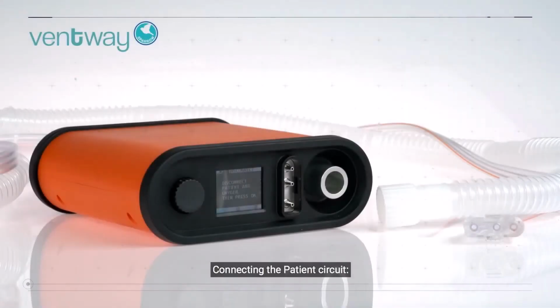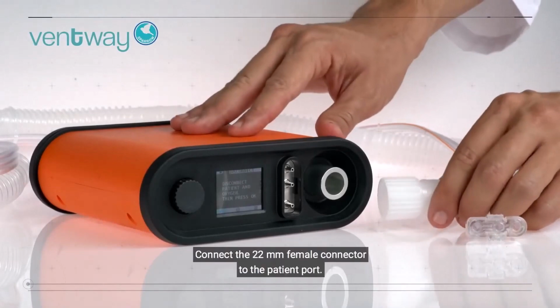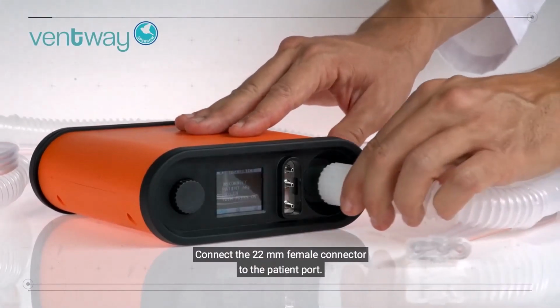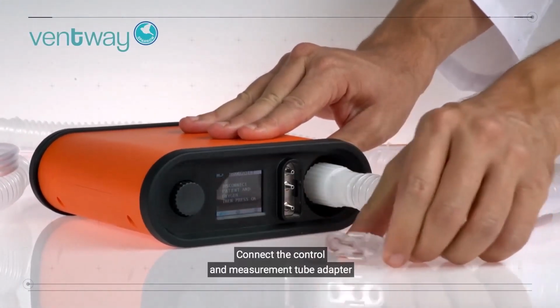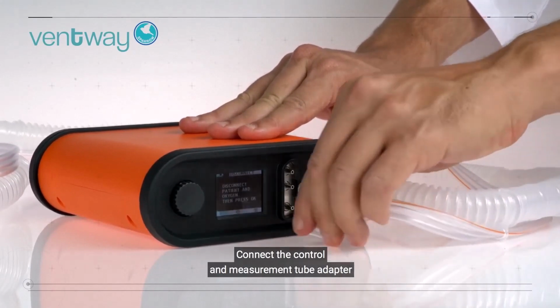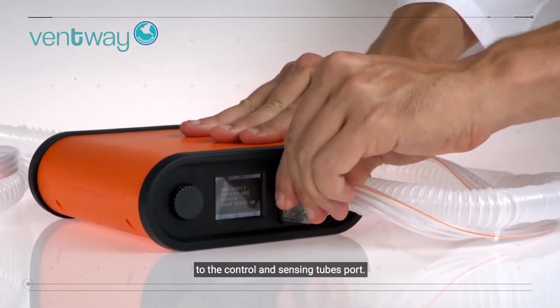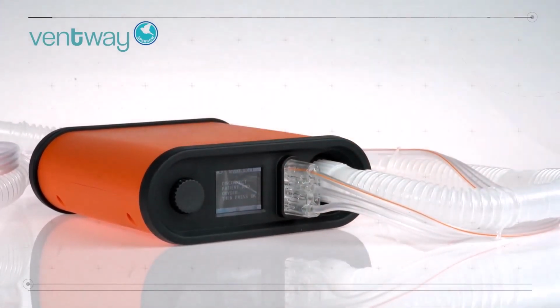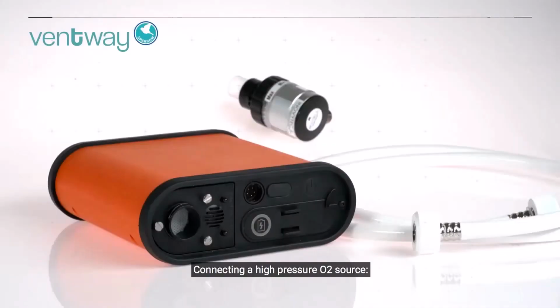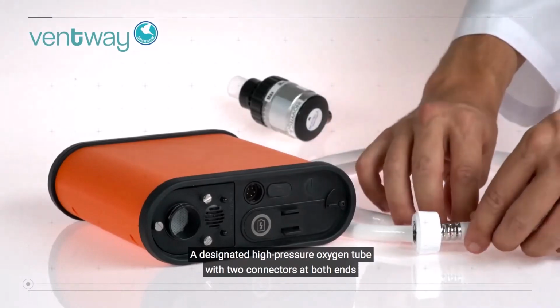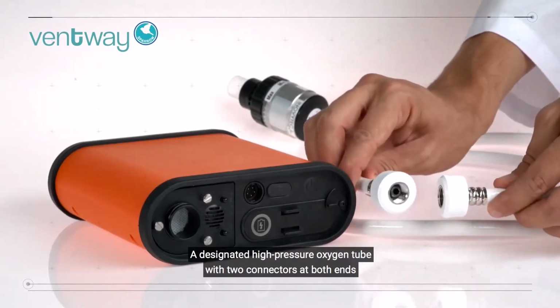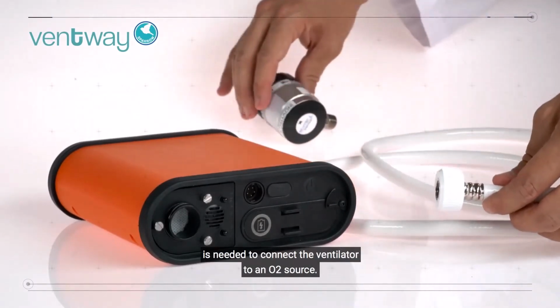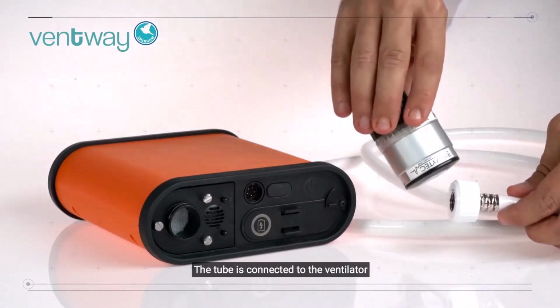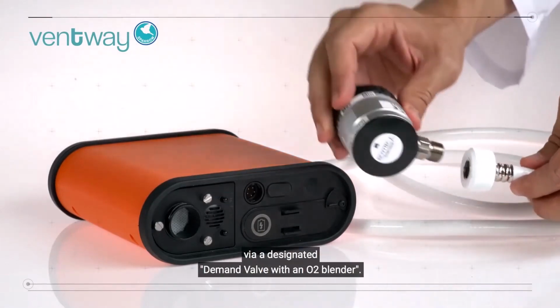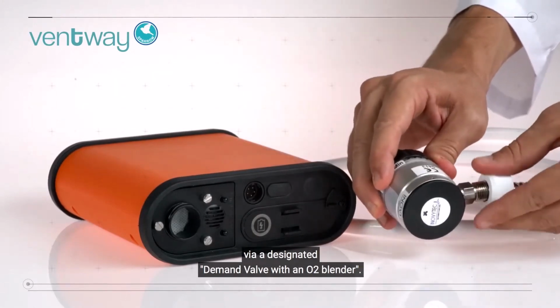Connecting the patient circuit. Connect the 22 mm female connector to the patient port. Connect the control and measurement tube adapter to the control and sensing tubes port. Connecting a high-pressure O2 source. A designated high-pressure oxygen tube with two connectors at both ends is needed to connect the ventilator to an O2 source. The tube is connected to the ventilator via a designated demand valve with an O2 blender.